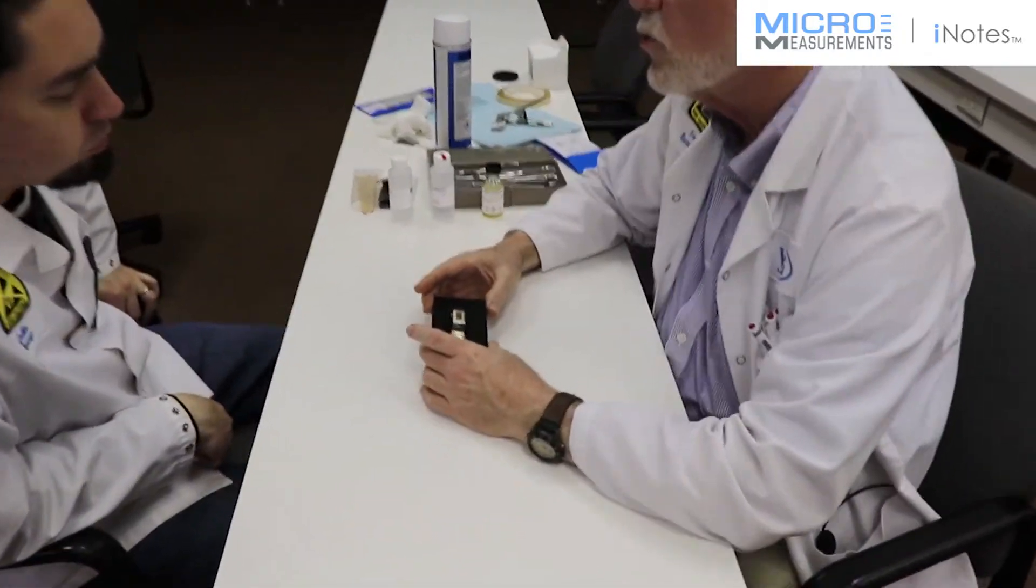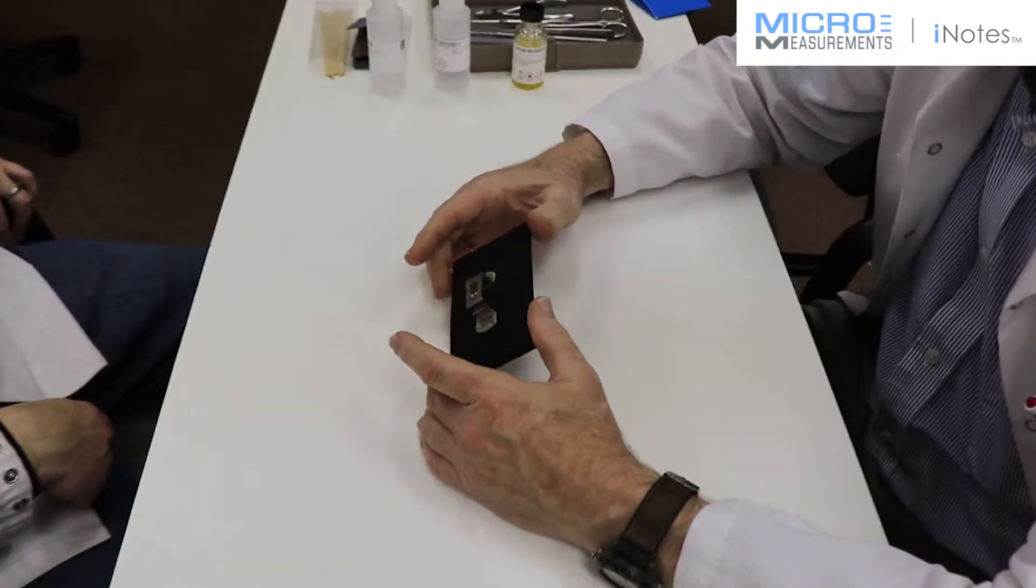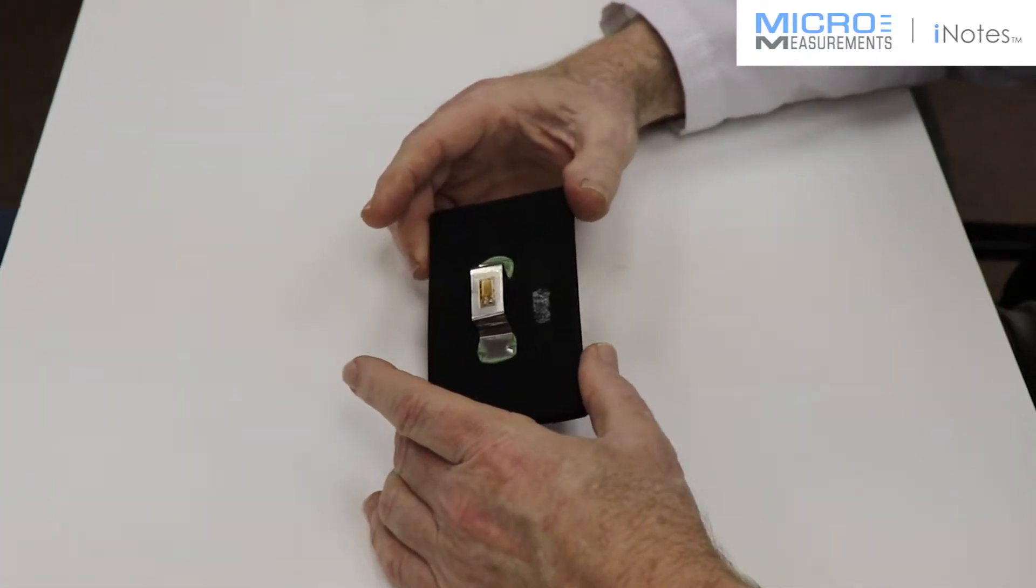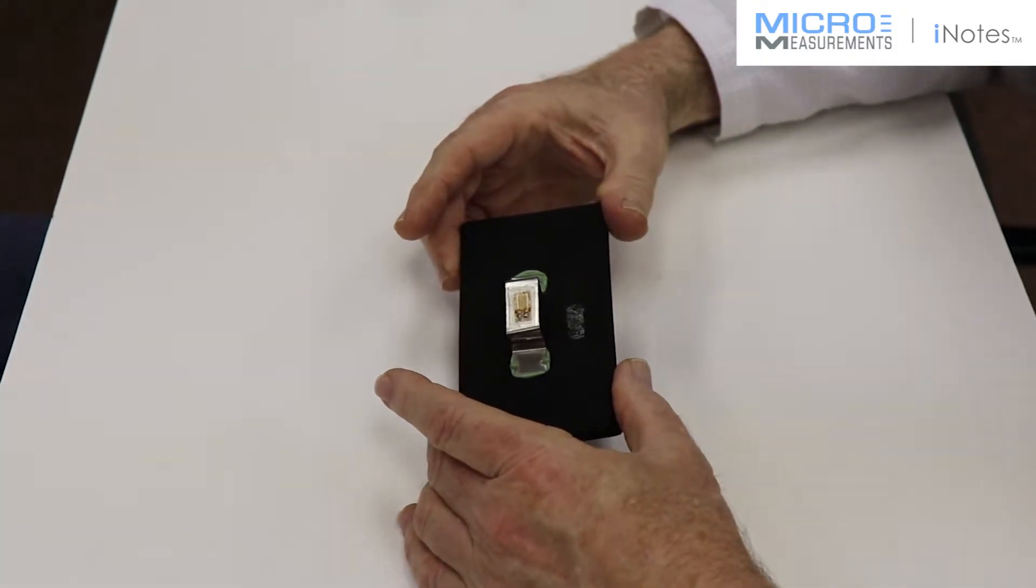A clip gauge is used when you encounter a situation where a bonded foil strain gauge cannot match the elongation capability, somewhere above 20% strain.